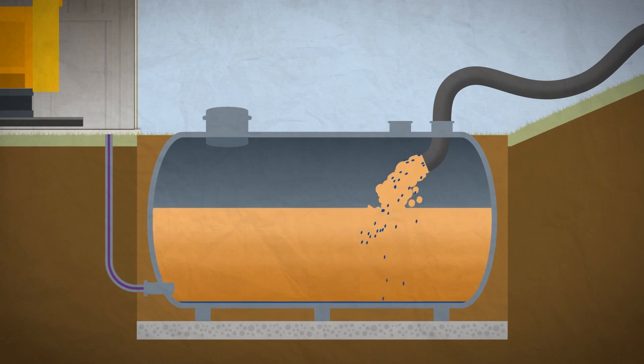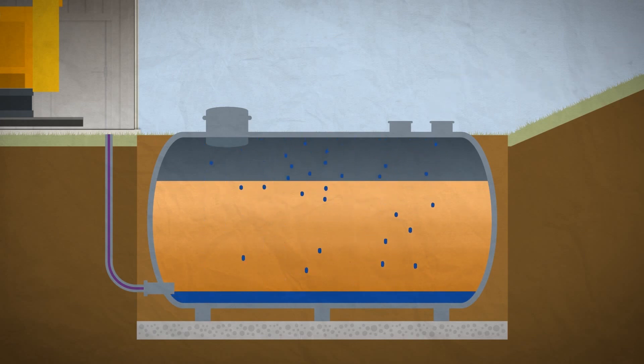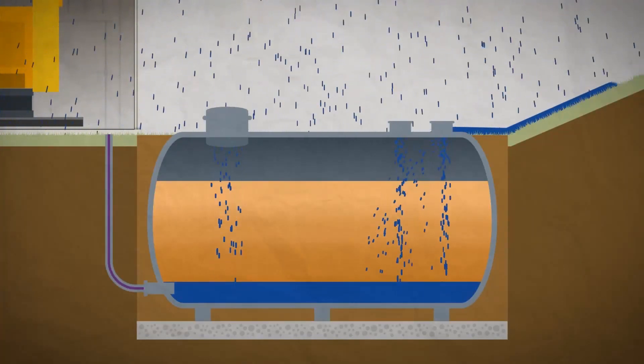Water can enter a fuel tank in a number of ways, such as the delivery of contaminated diesel from a supplier, condensation collecting inside storage tanks or vessels, rainwater entering through hatches or enclosures, and wash-down water through breathers or vents.